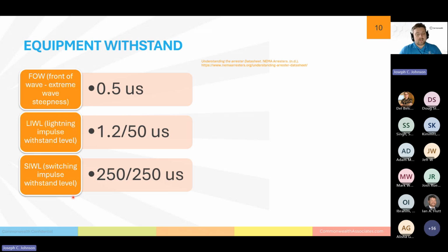So just talking about these waves now, these are the test waves that we do. I mentioned those before. We can't necessarily recreate a lightning bolt. We're not going to go out and make that happen. We're not going to open a bunch of breakers and see what waves hit it and test equipment that way. In a lab, we create these waves, and these are the waves that more closely resemble what we would expect to see. So the first is a front of wave. That's the extreme wave steepness test. That is a zero to crest time of half a microsecond.